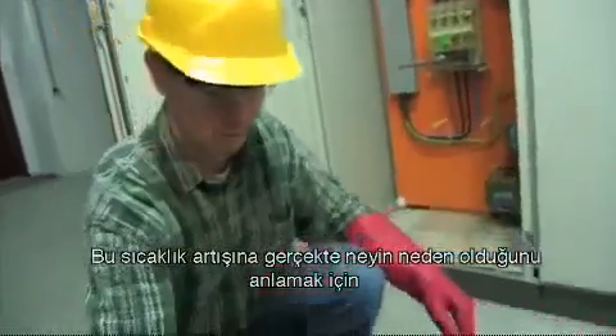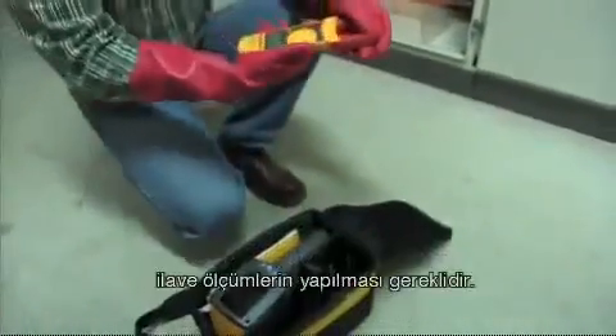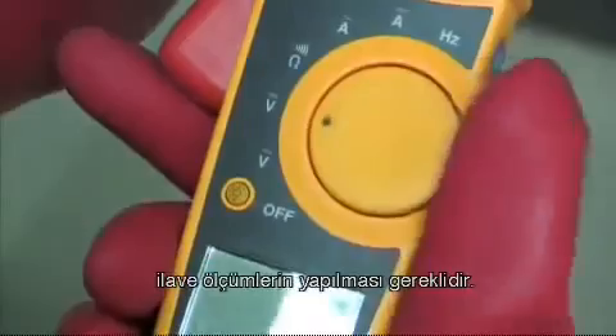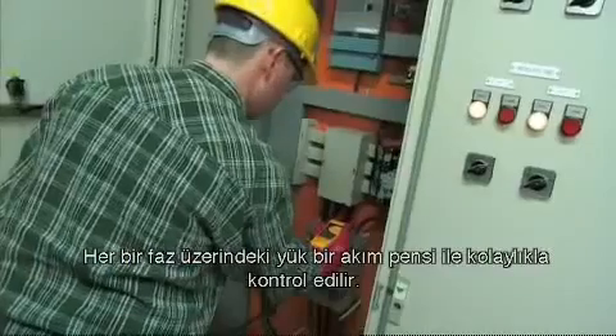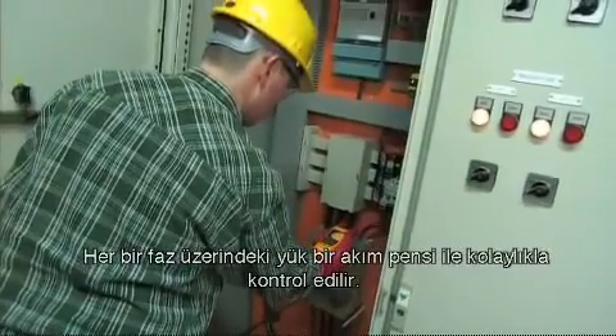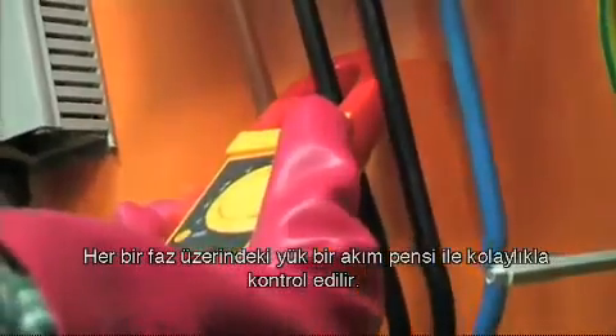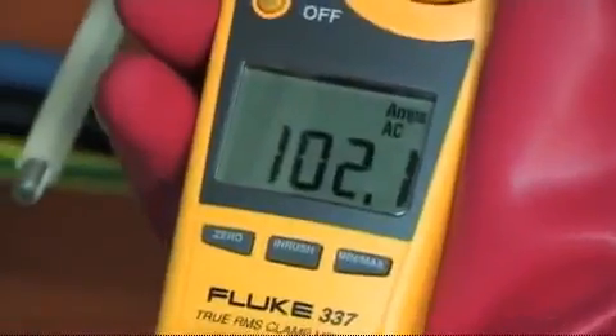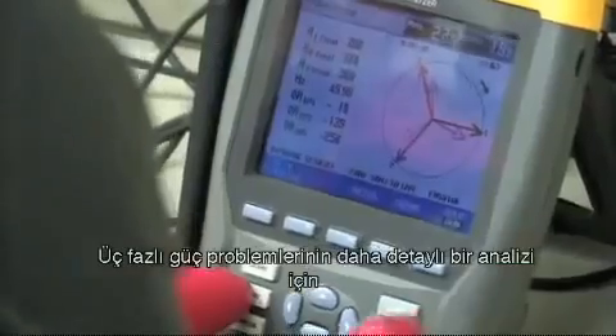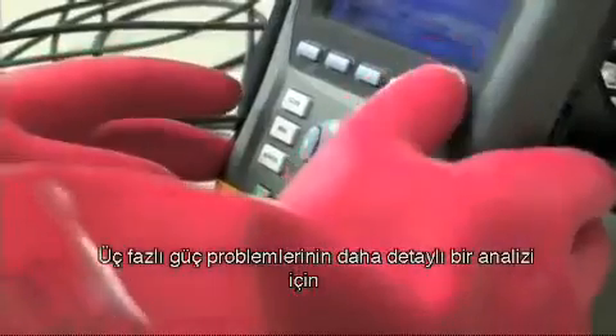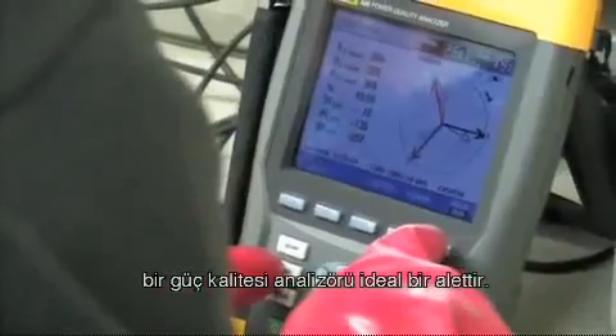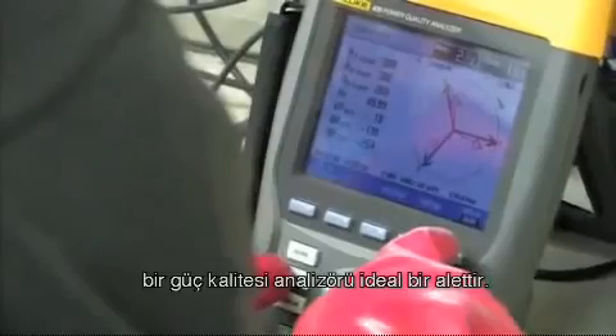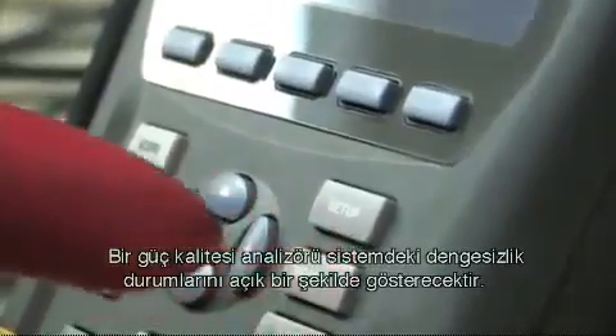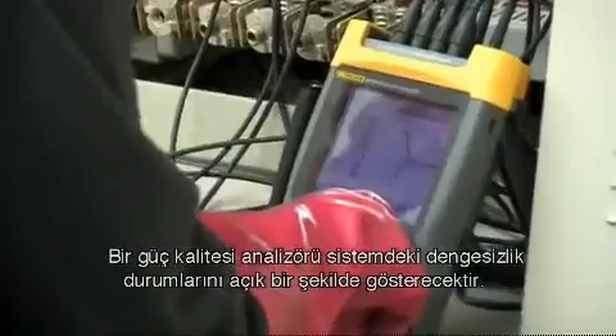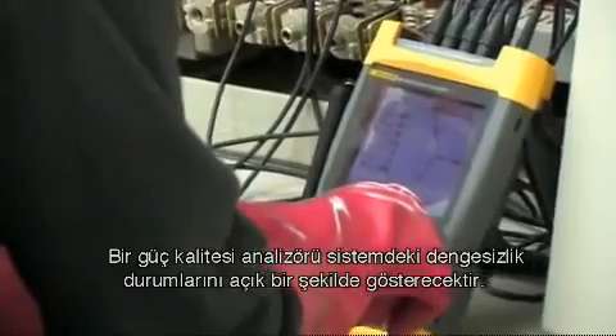To understand what actually causes this temperature increase, additional measurements need to be done. The loading on each phase is easily checked with a current clamp. For more detailed analysis of three-phase power problems, a power quality analyzer is the ideal tool. Hooking up a power quality analyzer will clearly show any unbalance in the system.